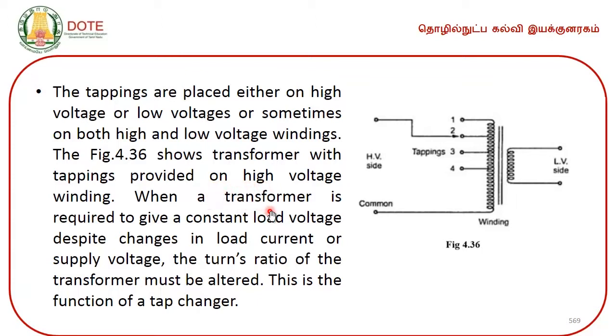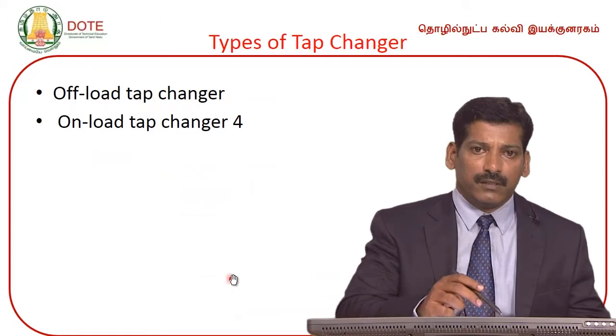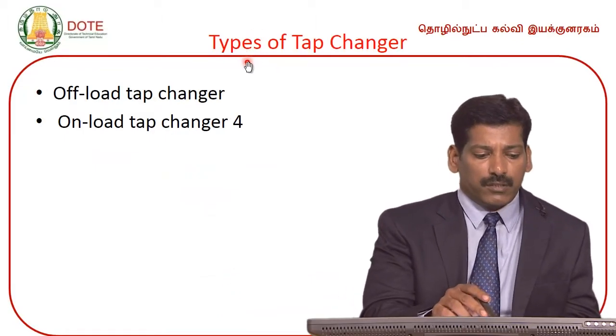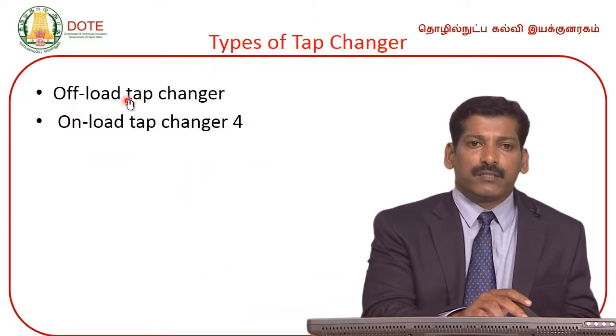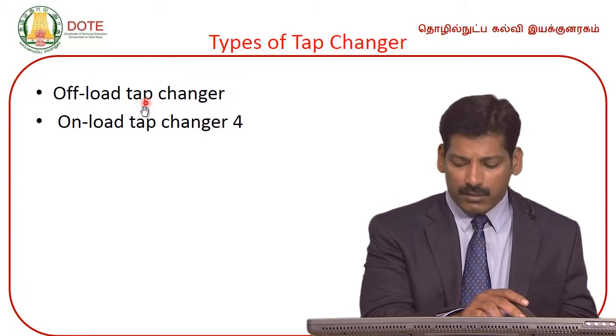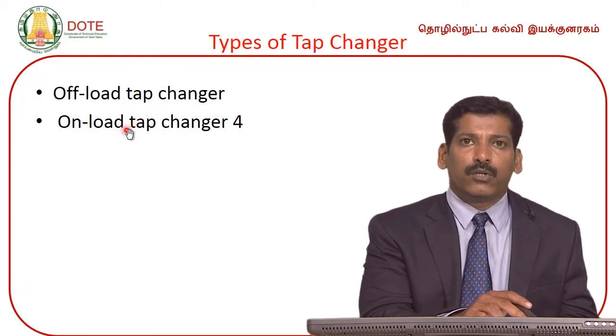When a transformer is required to give a constant load voltage despite changes in load current or supply voltage, the turns ratio of the transformer must be altered. This is the function of a tap changer. Types of tap changer: one is the off load tap changer, the other one is the on load tap changer.